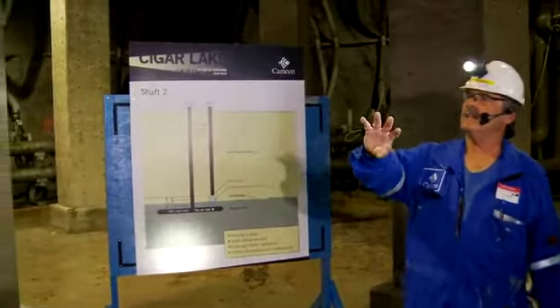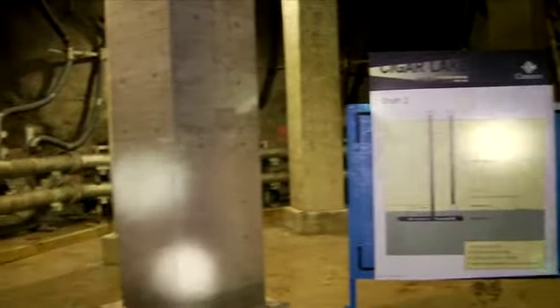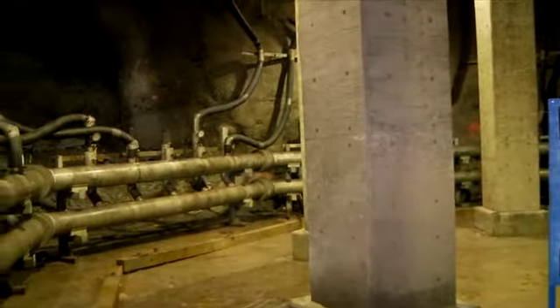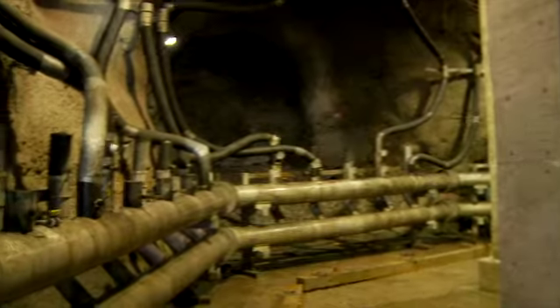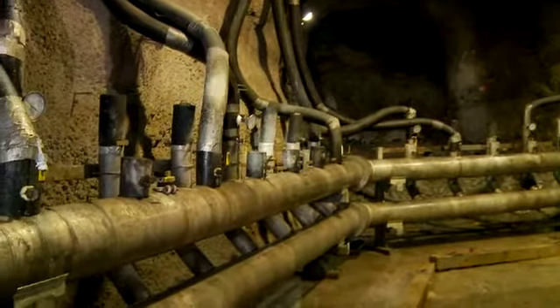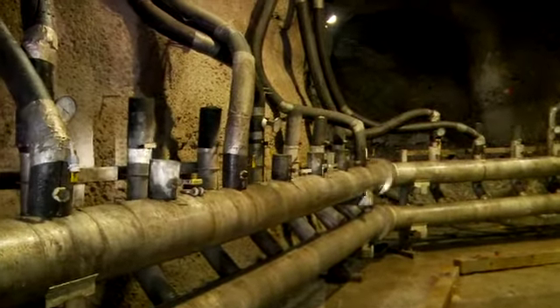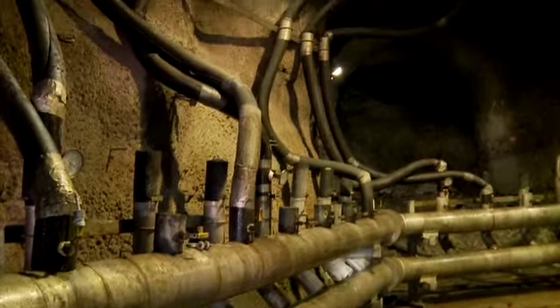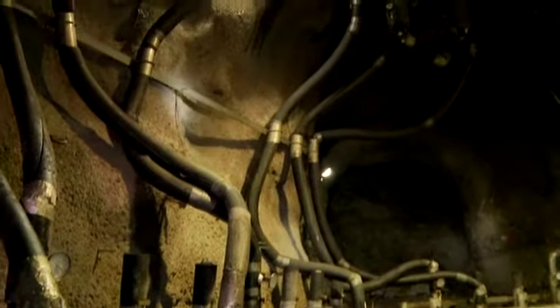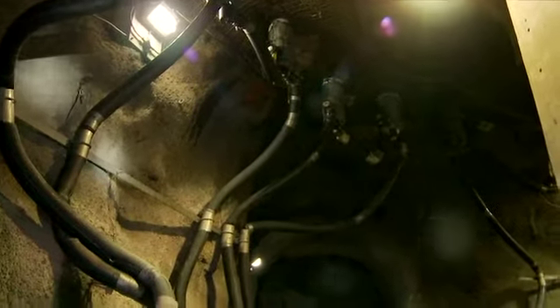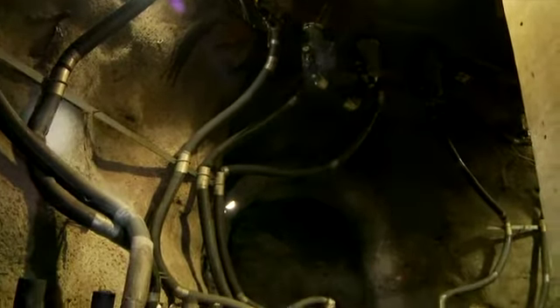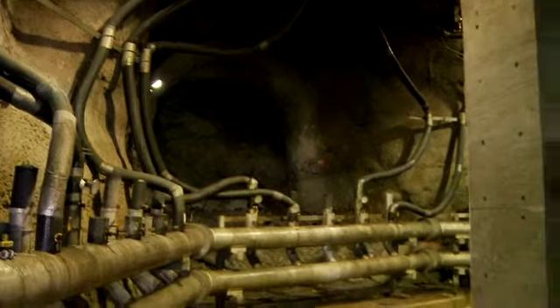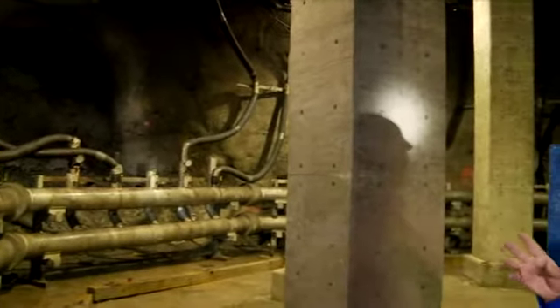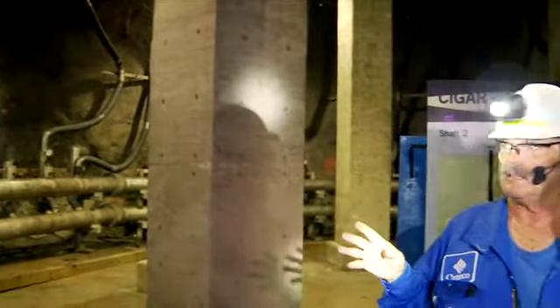First off, let's look at the freeze system that we have in here. For those that aren't familiar with freezing, we bring the brine down at approximately minus 38 degrees Celsius, and it goes through the manifolds here from the heat exchanger. The pressure in the manifolds is about 100 psi. That's key when we talk about the heat exchanger when we get there. Again, it's for safety reasons that you have it about 100 psi.